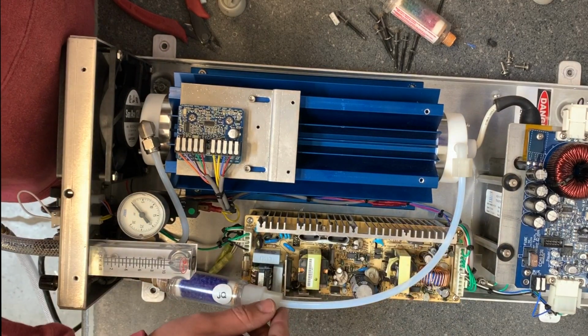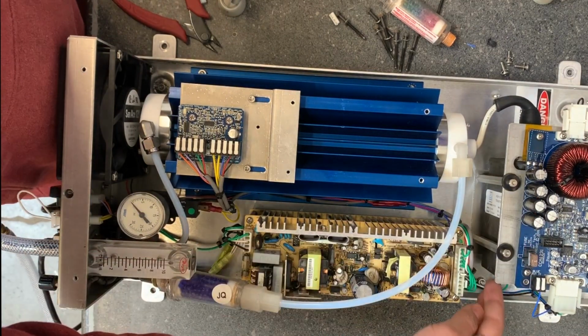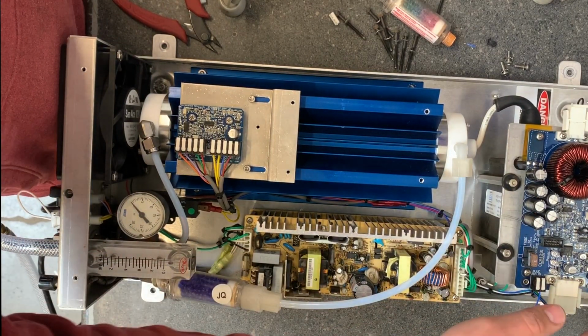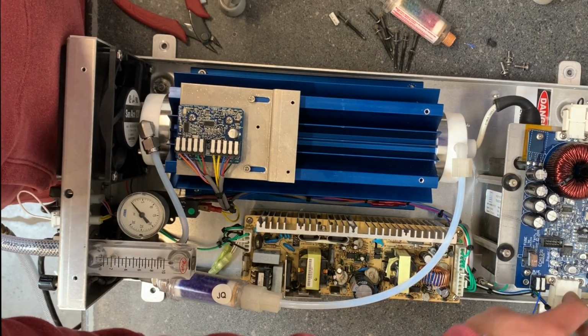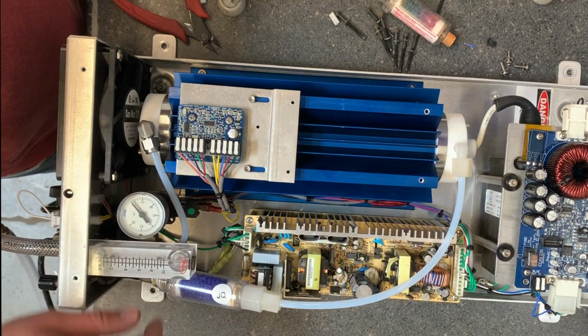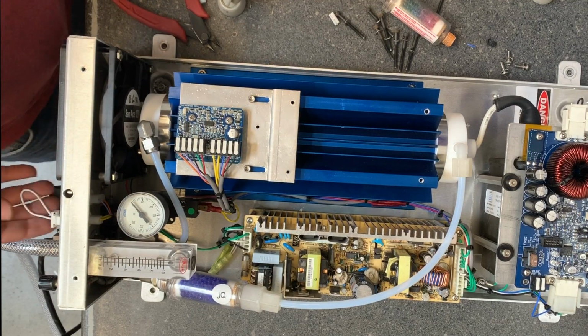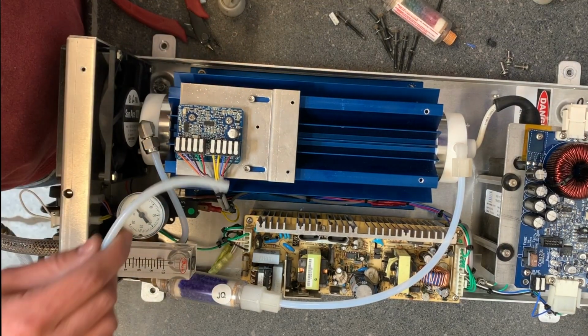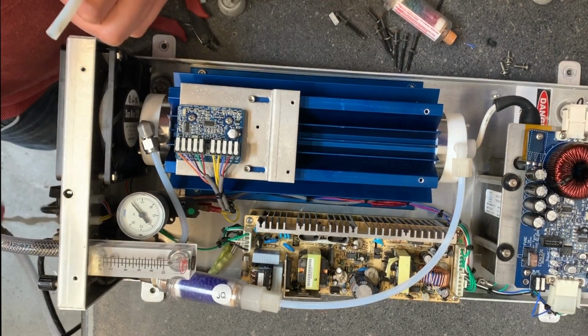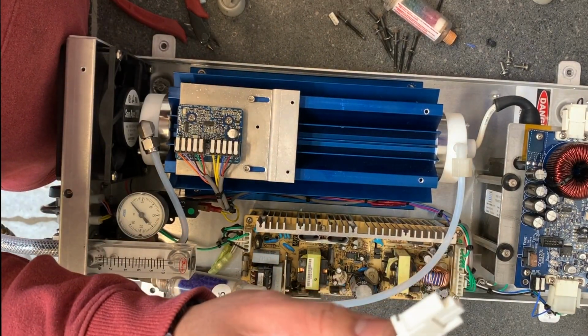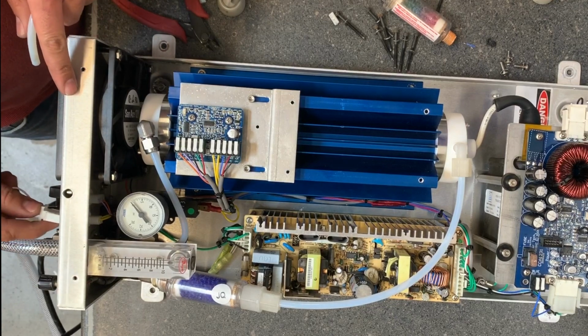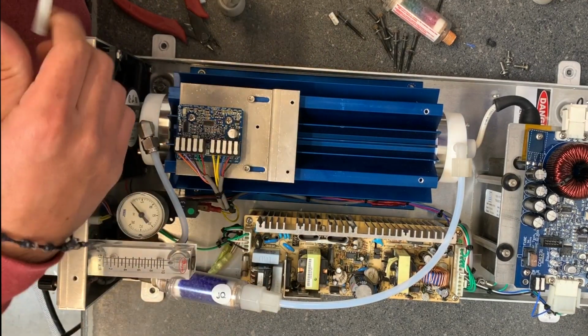You replaced hosing if you needed it. I replaced the transformer because this one was slushy. I did the shake test on it, reconnected all the connections, everything's back, it's mounted. So now we just have to satisfy the pressure switch, and this dry contact needs to be in play to satisfy the drive system to activate it.